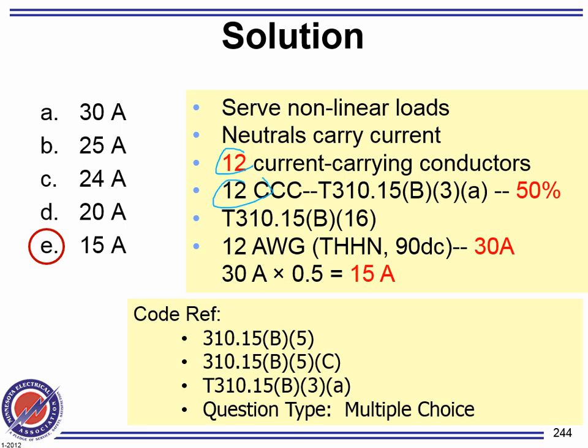Number 12 current-carrying conductor. The rating is 50. THHN under 90 degree can get you what? 30. So we're limited to 50. So each one of these conductors cannot carry more than 15 amps. Not only that, how can you guarantee that? You have to go there and put the 15 amp breaker on it, 15 amp breaker instead of a 20 amp breaker.